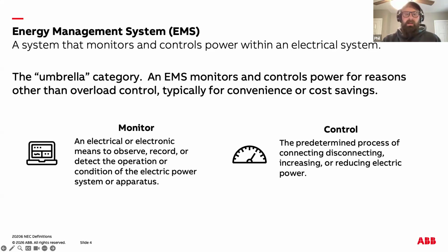So yeah, an EMS monitors and controls power within an electrical system and serves as the umbrella category for both EMS and PCS. The 2026 code clarifies that EMS functions are for purposes other than overload control. This is an important distinction. EMS is not for overload control. It's more typically for convenience or cost savings. So to avoid confusion, remember that monitoring means observing, while controlling means actively directing power flows.